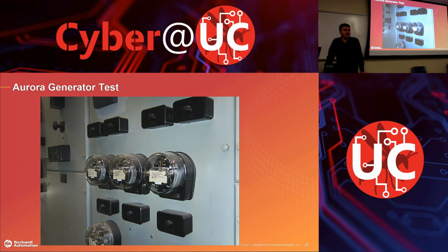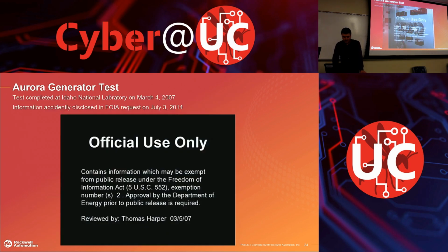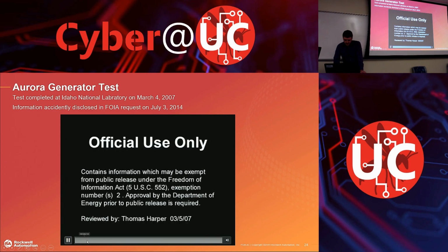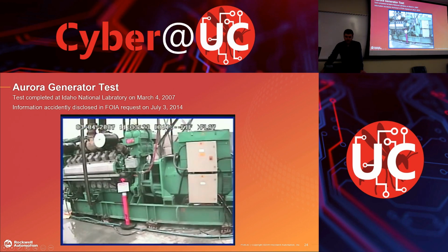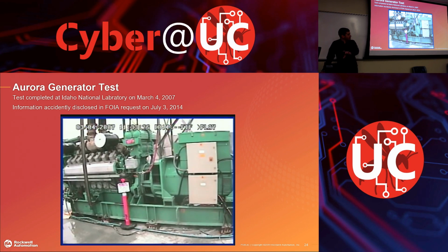When you've got a magnet that's out of phase with the power it's trying to keep up with, it tries to line itself up really, really fast. And when it can't physically line itself up fast enough, and it weighs a whole lot, all that power has to go somewhere - and that somewhere is the rest of the machine. So if we go back here - each time that machine sort of jumps up and down, they're sending a command to disable that protective relay, let it run freely for a few seconds until it's out of phase, then close it again so it tries to snap back into place, which it's not designed to do. If you do that enough times, you eventually break something important, and you get this.